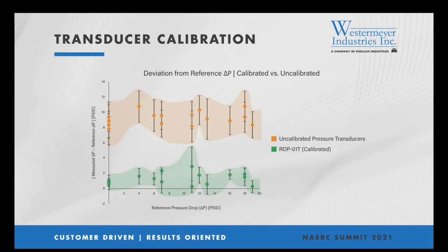Now, I'm sure you all observed on the previous graphs that the inlet pressures are lower than what we would anticipate for transcritical CO2 applications. This graph presented here is a variation of the bar chart presented in the previous slide and is meant to illustrate that the results are not dependent on the separator inlet pressure. The results are plotted here as the average value of the difference between the pressure differential and the reference pressure differential versus the reference pressure differential itself.